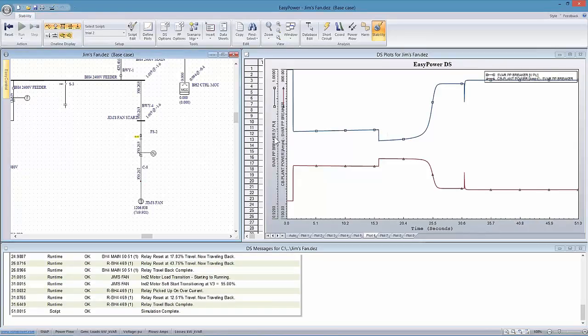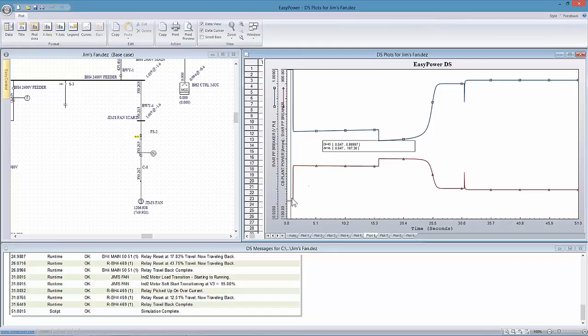Now again, these are somewhat artificial in that I haven't totally modeled the whole plant, but you can see that we're starting to get our desired result. Again, we're starting at 197 as far as the total current in the plant, and then we go to a max current of 386, 385, and then up to a little bit over 400, 420, and now this period lasts for 10 seconds. So there still needs to be some tweaking done, but the point is I have control, or I have the ability to kind of mitigate what's going on.